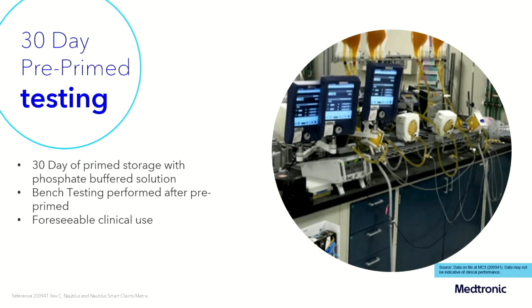If you look at your cardiopulmonary bypass oxygenator, the IFU specifically tells you that you're supposed to use it immediately after priming. You're not supposed to prime it and let it sit, right? Because they haven't tested for that. In this, they did 30-day pre-primed storage with this phosphate buffered solution before any of the bench testings to validate that all the gas transfer and everything is still efficient after this.